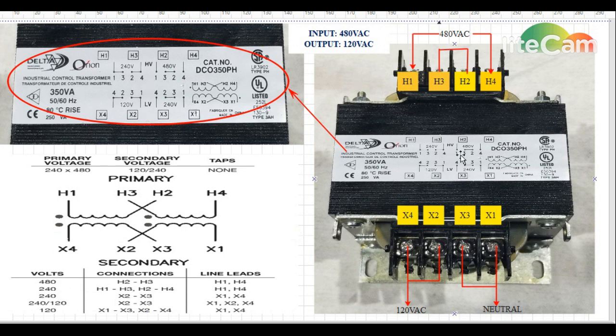So now let's have a look at the secondary side of the transformer, the secondary terminals where we need a 110 as output. To obtain a 110 as output from the secondary terminals, we will be wiring according to this drawing over here. As you can see in the drawing, 4 and 2 are jumpered together, so X4 and X2 are jumpered together. And 3 and 1, that means X3 and X1, will be jumpered together, and we will be getting the output from terminal X4 as a 110, and the output from terminal X1 as a neutral.